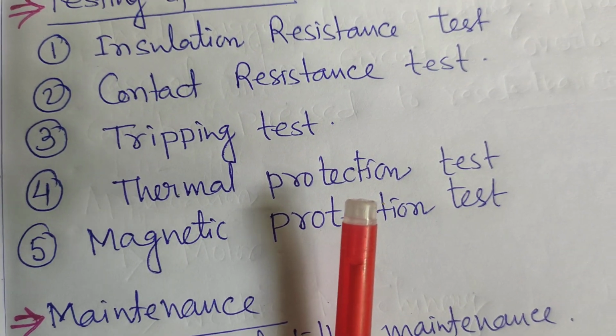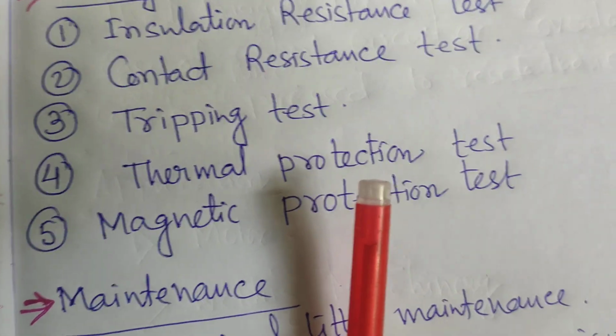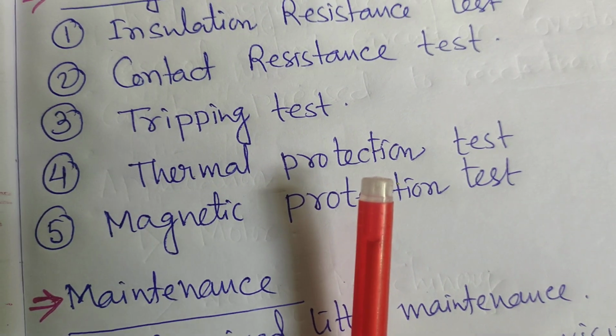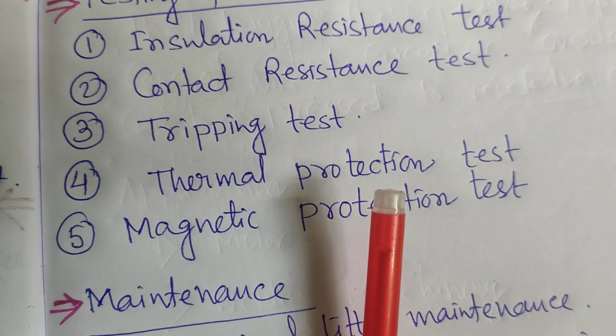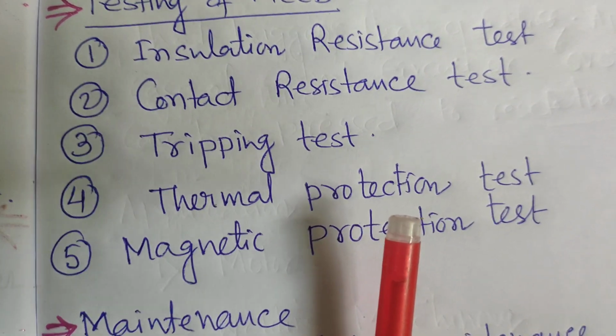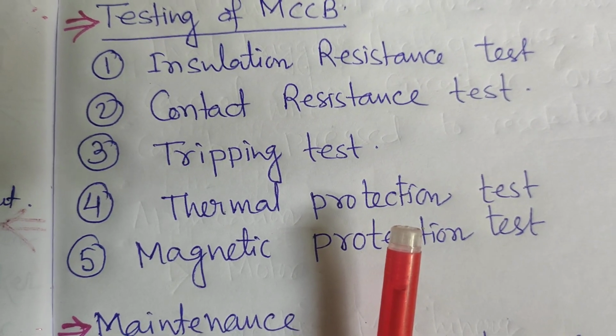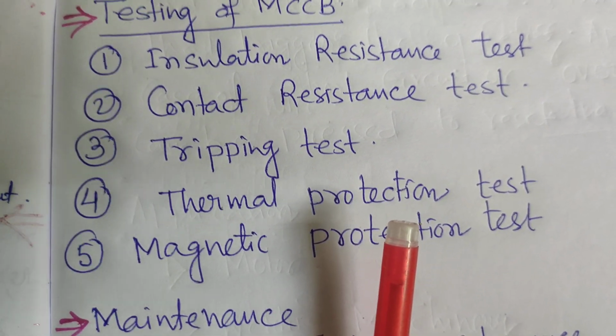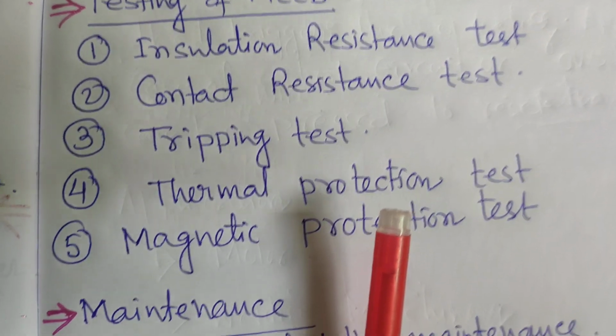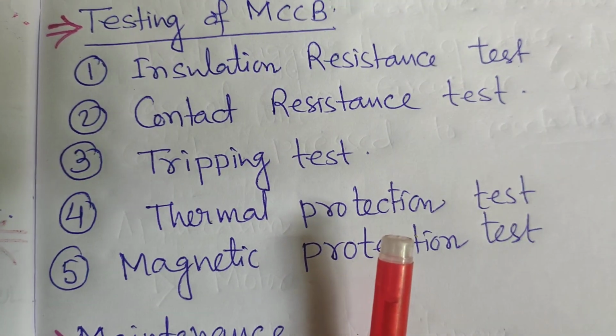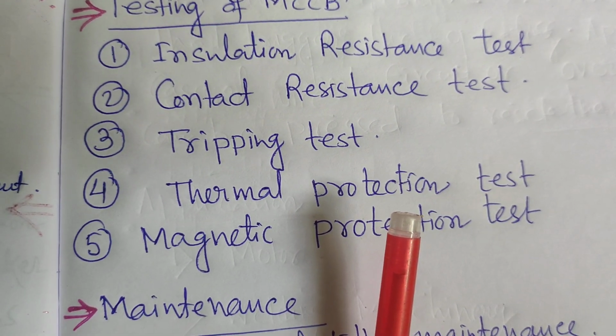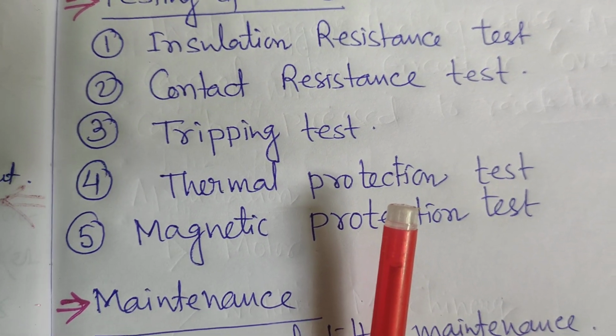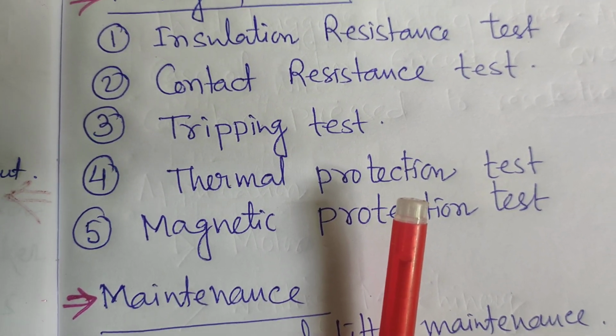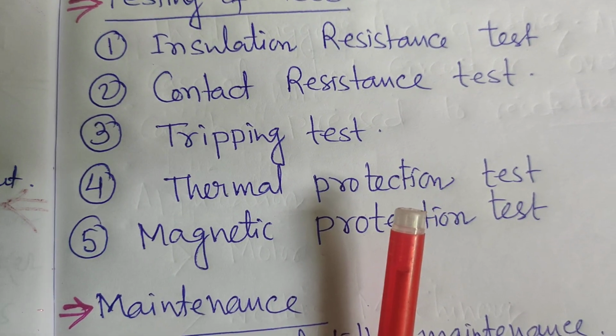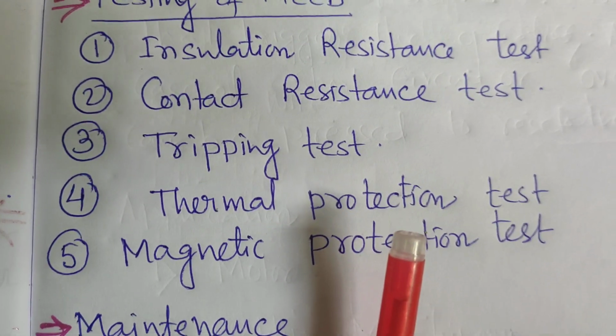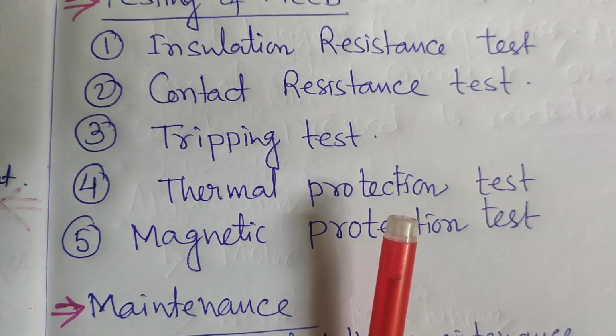If the MCCB has been designed for 2 to 3 times current, and 10 times current flows, heat will be generated, and the heat will bend the thermal strip, and that thermal strip will be disconnected from the connecting part, so the MCCB will be tripped. This is the thermal protection. And for the magnetic protection, if a lot of current flows, the magnetic solenoid will be energized, and if the magnetic solenoid is energized, it will automatically trip the circuit breaker.